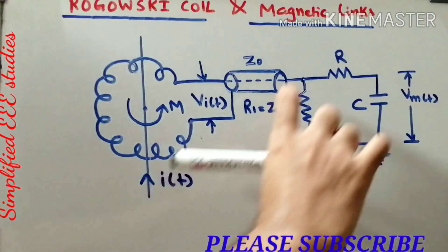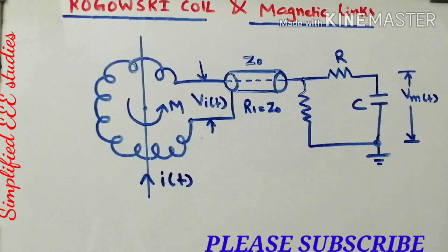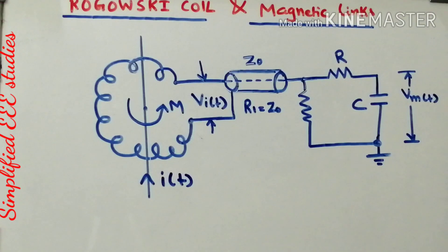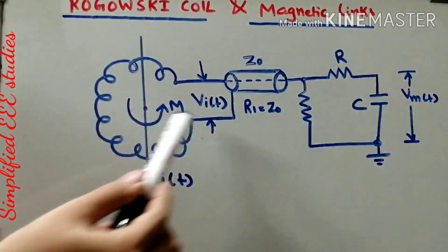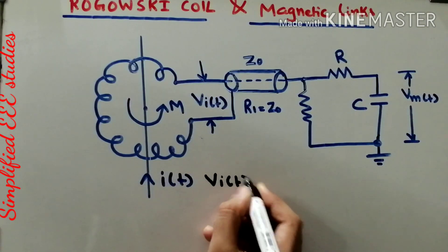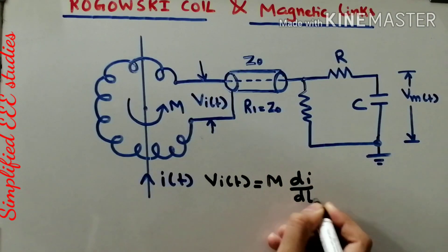If you connect an integrator, you can get the total voltage at the CRO. The voltage induced in the coil, VI, is proportional to the rate of change of current in the straight conductor. This can be calculated by applying Faraday's laws of electromagnetic induction. VI is given by M·di/dt, where M is the mutual inductance of the Rogowski coil.